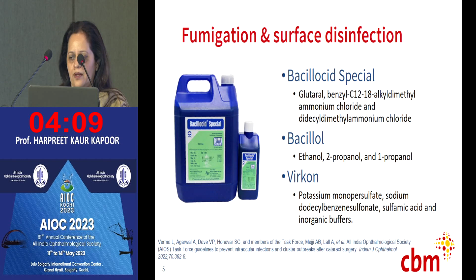As for the surgical instruments, a rigorous sterilization protocol has to be in place for sterilizing instruments, because that is also one of the major causes leading to an outbreak. So autoclaving, as we all know, is the gold standard, and of course ETO for certain instruments. And in a high volume setup, you should have several instrument sets so that they can be autoclaved in between cases.